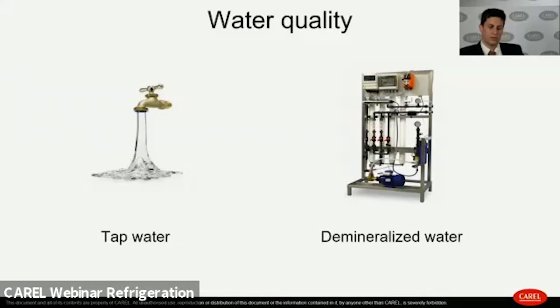Demineralized water is another option. It is treated water, and the property of demineralized water is to have a really low mineral content. So when we spray this kind of water, we do not spray minerals, and we avoid any kind of mineral deposits and limescale issues. Anyway, with this kind of water, the installer and the designer need to consider that it can be aggressive water against aluminum, for example. So it has to be considered for the installation whether the heat exchanger materials are compatible with the demineralized water.